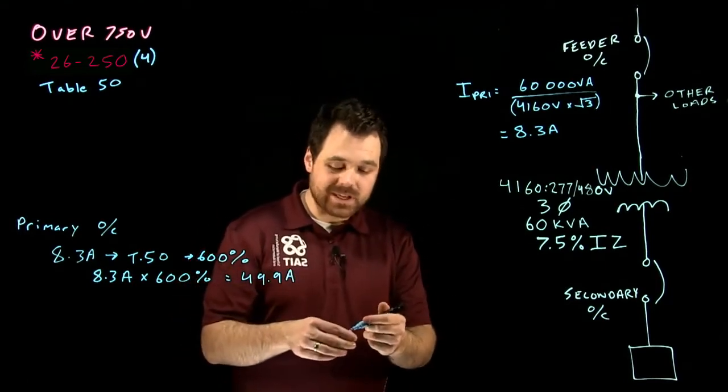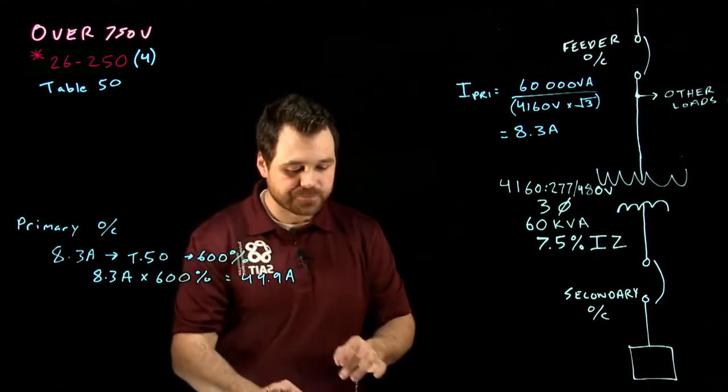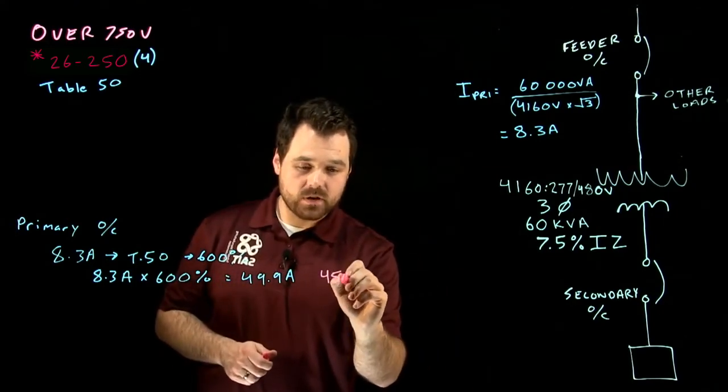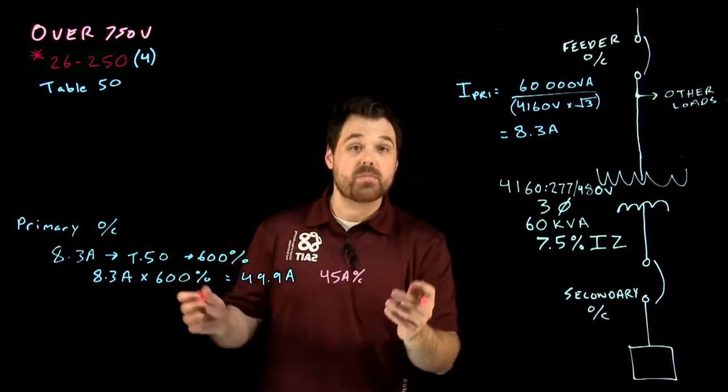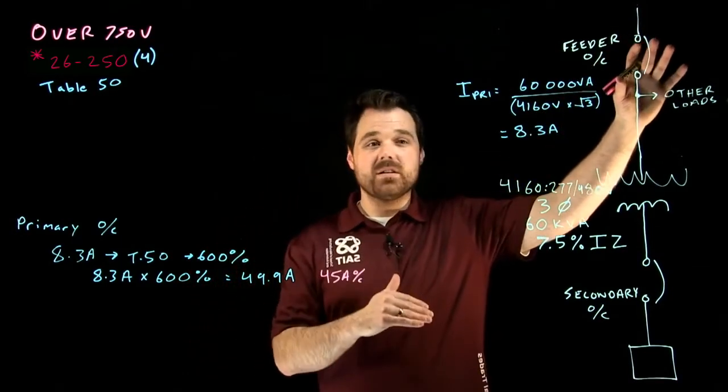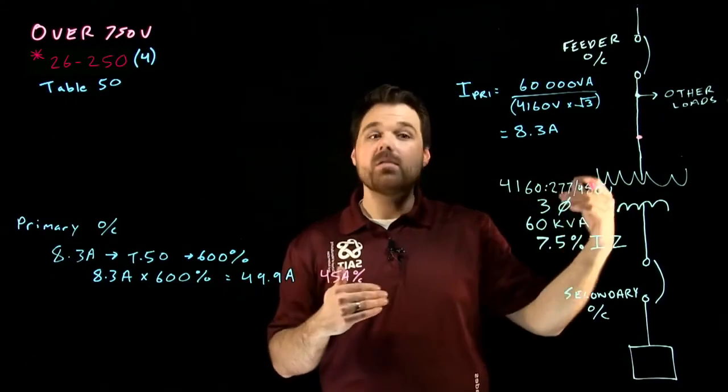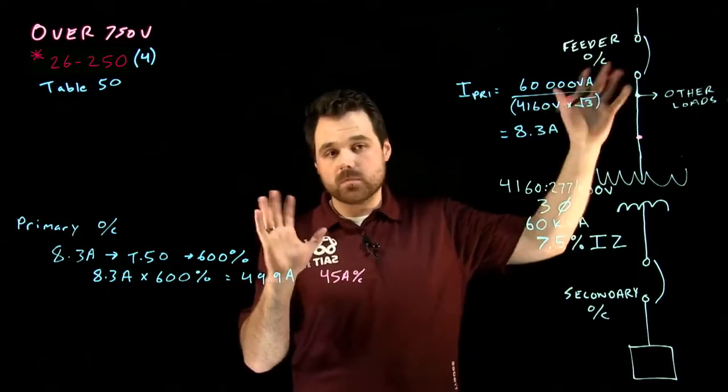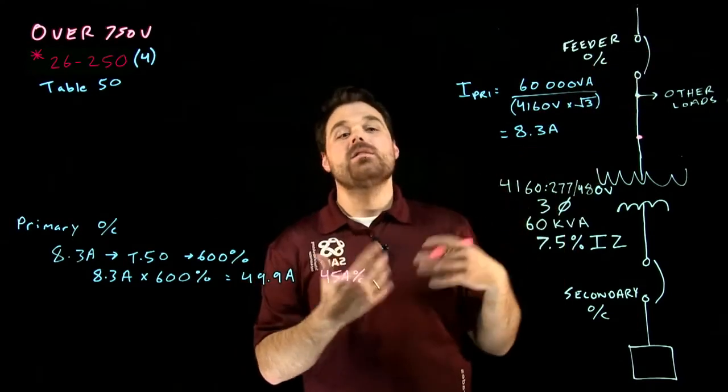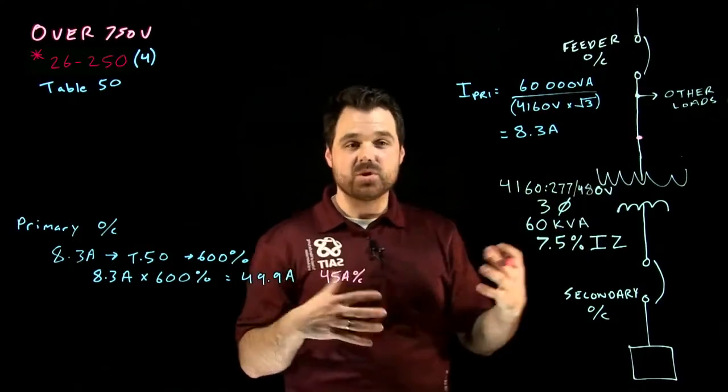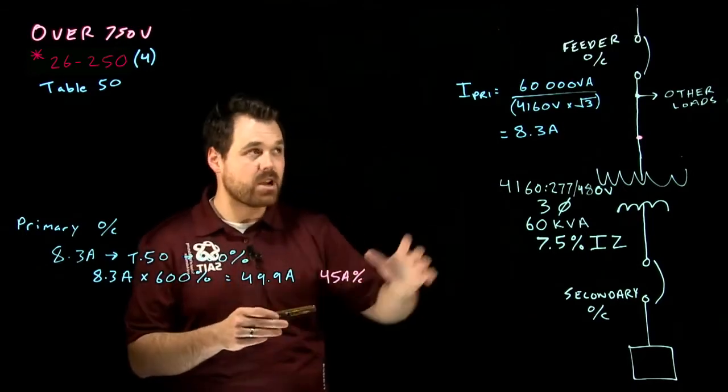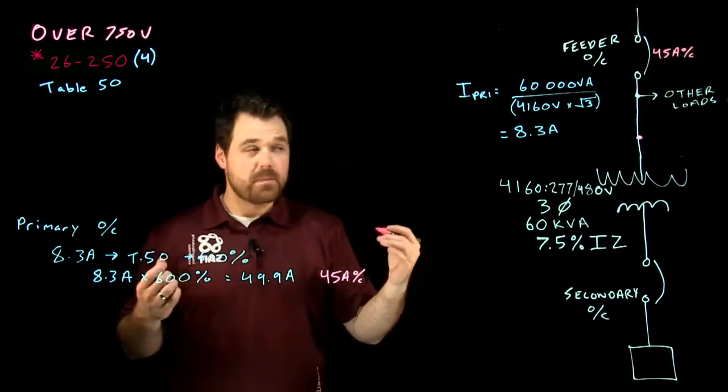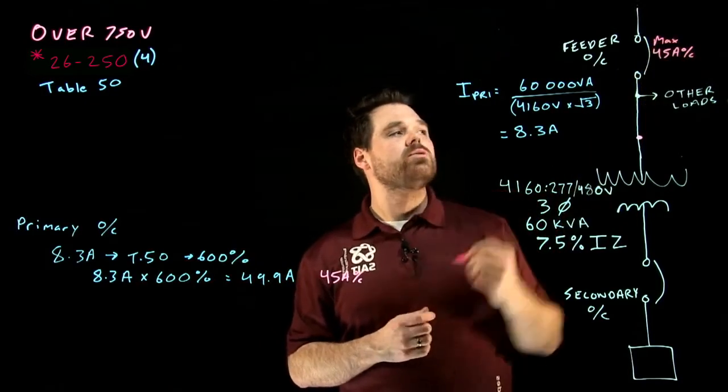The rule says we cannot exceed 600% the rated primary current. Once we take that to table 13, table 13 would tell us a 45 amp overcurrent device on the primary. So if this was greater than 45 amps, we would require one there based off of subrule 1 using that calculation. Either way, if this is 45 amps or less, then we are good to go and we do not need an additional individual primary overcurrent device. That's how we would size that or make sure that this one is okay. I'm going to say that this is 45 amps. That would be the max OC, 45 amps.